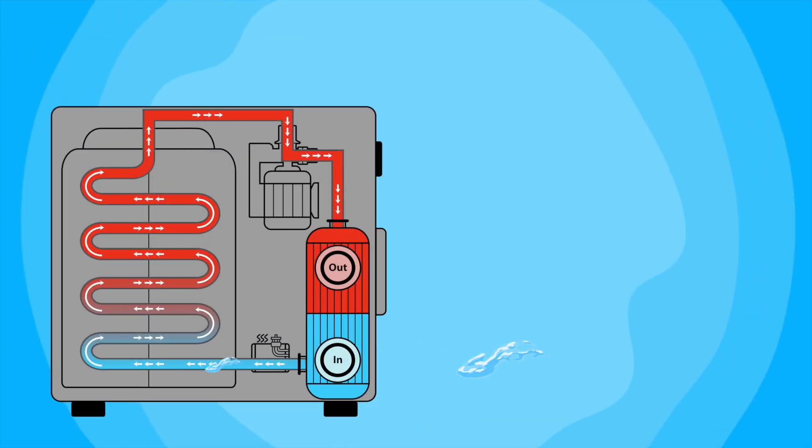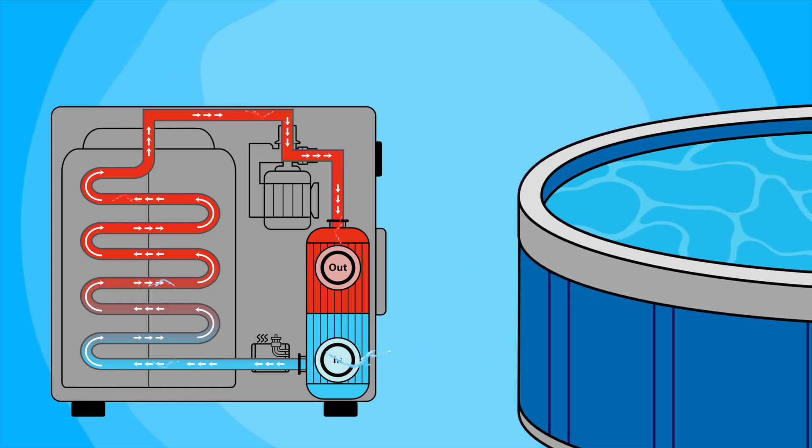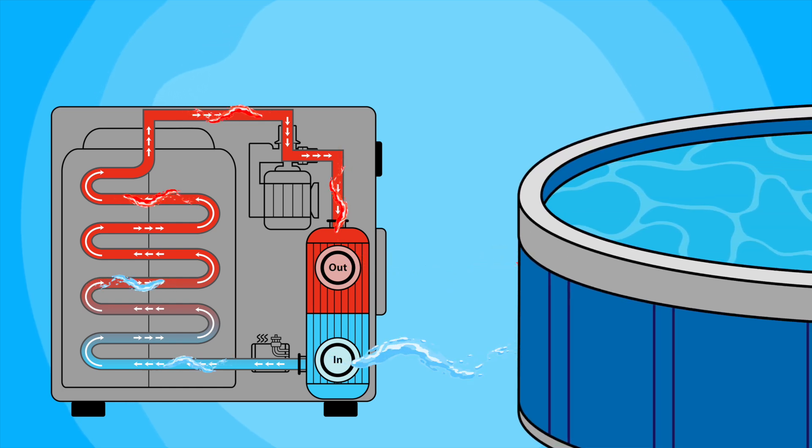Meanwhile, the cooler pool water is circulated through a heat exchanger, where it absorbs the heat from the compressed refrigerant gas. This exchange of heat causes the refrigerant gas to condense back into a liquid form. The now warmed water is then pumped back into the pool, and the process repeats.